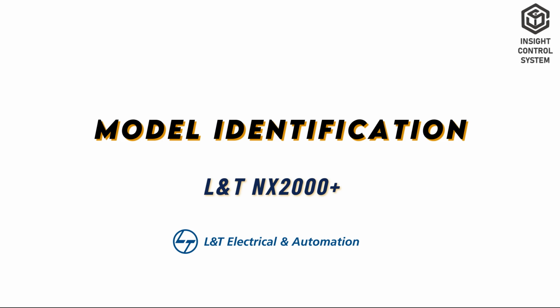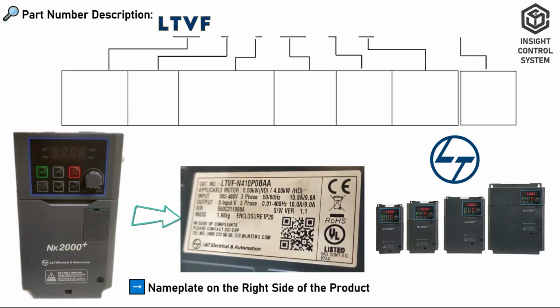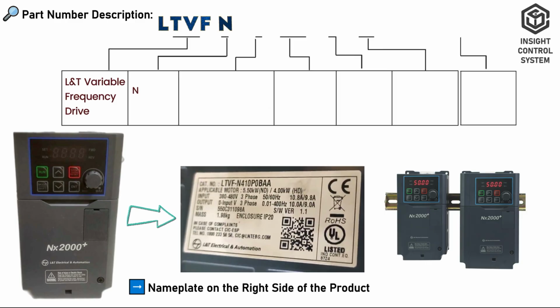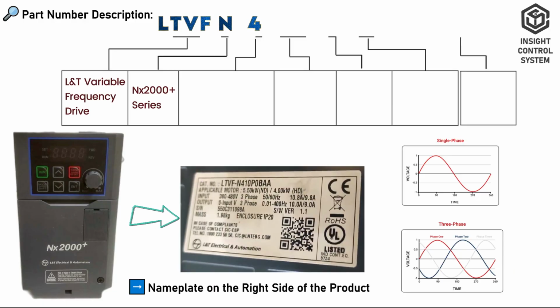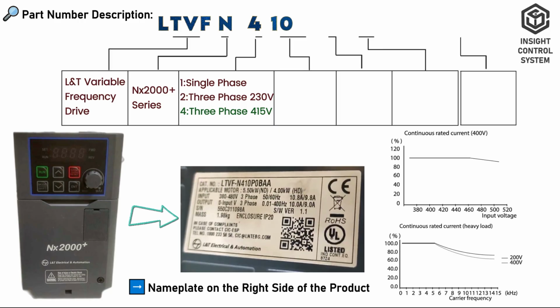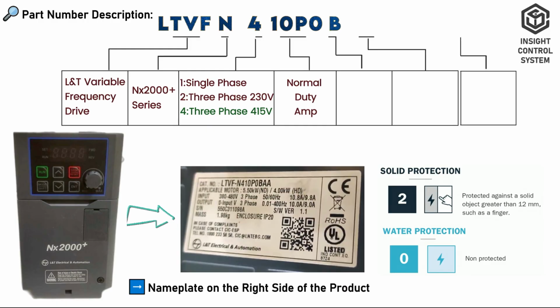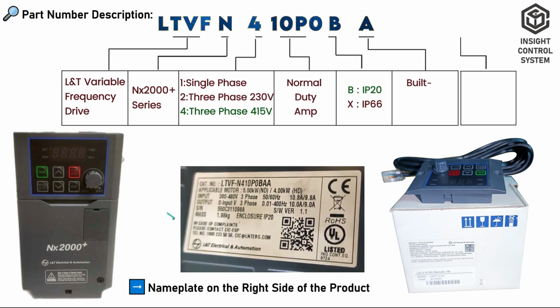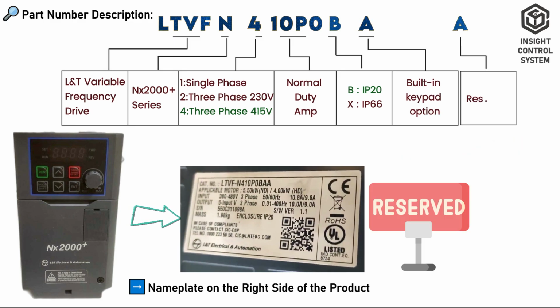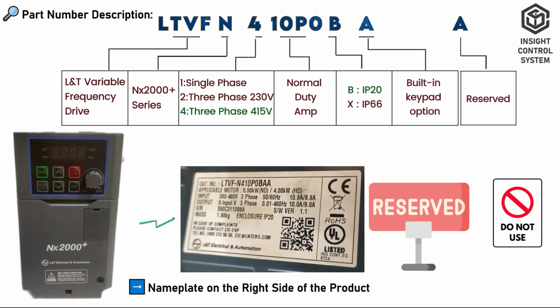Model identification. The first 4 letters define the drive name, which is L&T variable frequency drive. The next letter N denotes the drive series, which is the NX 2000 Plus series. The next digit, 4, represents the drive input phase and voltage range. The next 4 letters indicate the VFD drive's rated or full load current. The next letter B indicates the ingress protection, which is IP20. The next letter A denotes the built-in keypad option. Last letter A is the reserved option, which indicates do not use or for future use.